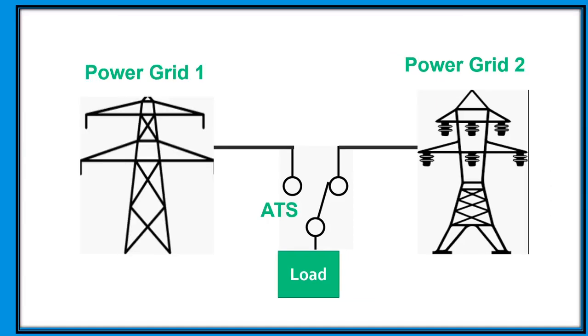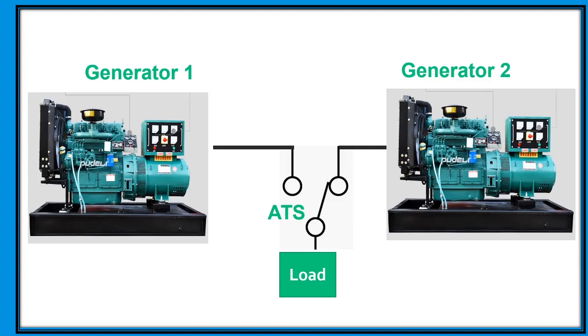The second one is power grid utility to power grid utility. In this case, two utility sources supply redundancy in the distribution system and allow for a quick restoration of service to the load if upstream equipment failures occur. The two sources can be independent of each other. And the last one is generator to generator — two generator sets for prime power use, often at a remote operation. The generators may be required to provide continuous power 24/7 to equally share run time, and source power is periodically alternated between generator sets.